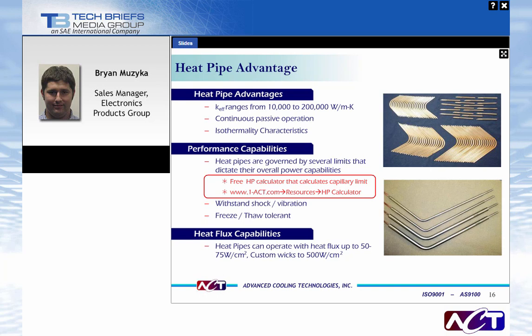A heat pipe will typically have somewhere between a two to five degree temperature difference across its length, which at pretty much any length gives you increased performance over a bulk metal. The big advantages of a heat pipe are effective thermal conductivity — ranging anywhere from 10,000 W/mK for a short six-inch pipe to 200,000 W/mK for longer pipes used in satellite systems. They're passive, so no additional power or cost is added to your system. And they provide good isothermality, keeping things at very constant temperatures.